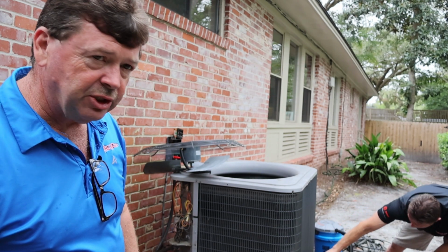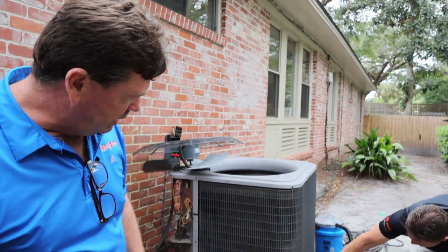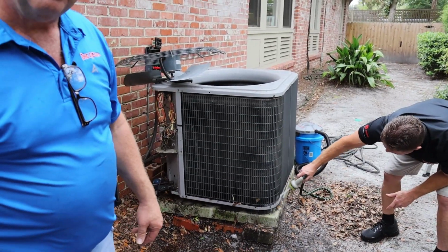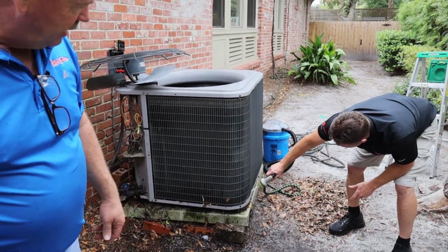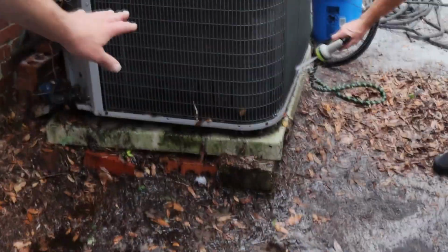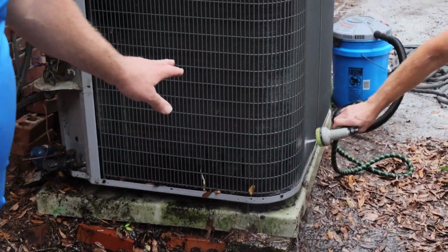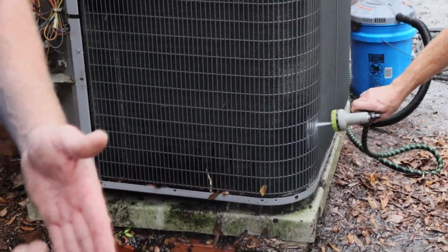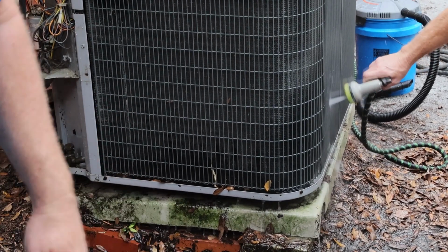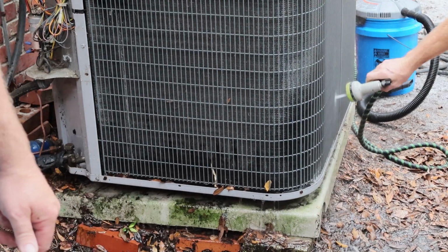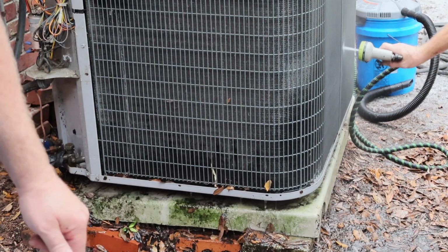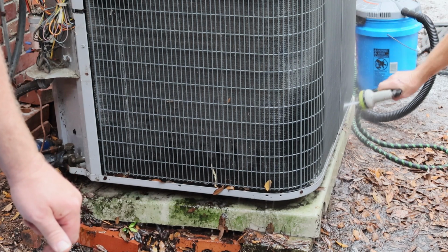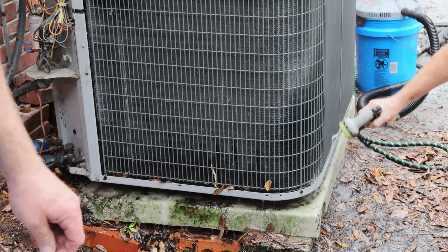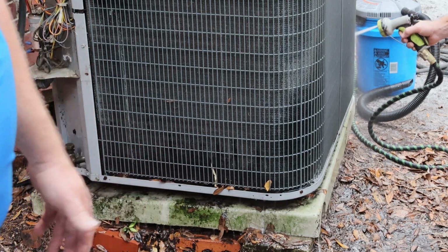Dave's washing the condenser coil out from the outside and the inside so we can make sure we get everything that's trapped in there. If you notice, the fins are real thin. So the dust sometimes gets stuck in the middle, so it doesn't look as dirty, but over time it can get pretty dirty. So keeping it clean at each maintenance is crucial to make sure the machine's performing properly.